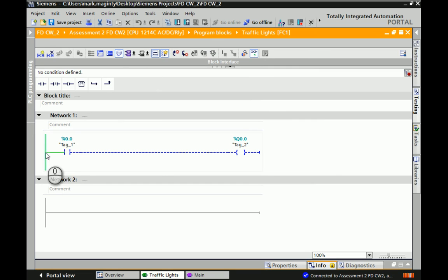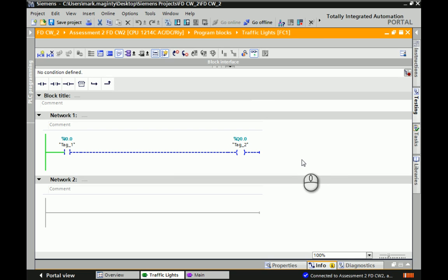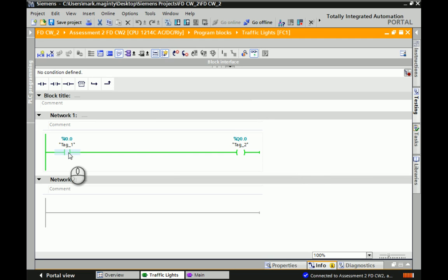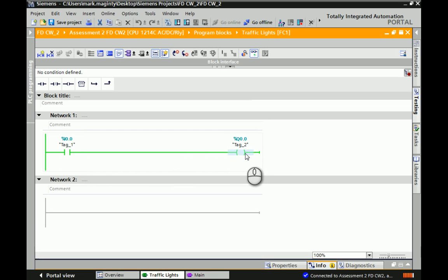You'll see the banner turns orange at the top. That's the indication from Siemens that you're currently online, you're live with the particular system. Then, anywhere where the green icon here on the left turns green shows you, basically, where the voltage is. Obviously, we're not working with voltages here, it's within a program, but it's an easy way to think about it. If we activate I0.0, I have a cable here to help short out. I'm going to put 24 volts straight into input 0.0. You can see as soon as I've put the cable into it, it recognizes I0.0 has become active and it's turned on Q0.0.